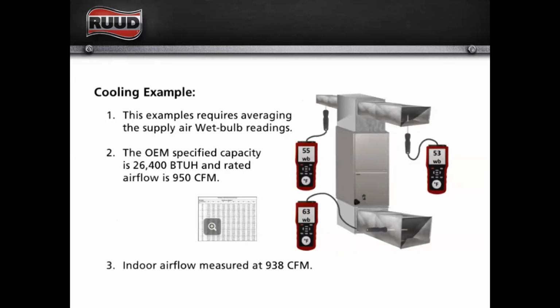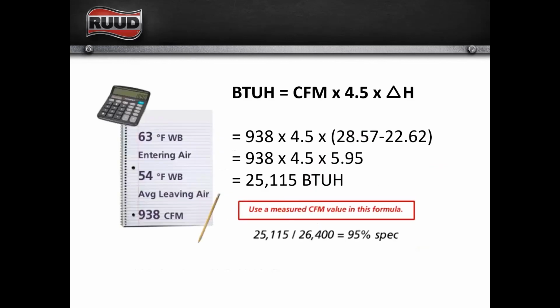Okay, so this is using CFM that we've got rated right here. So here's our example, right? We have got a manufacturer's specified capacity of 26,400 BTUs. Rated airflow is 950 CFM. Our actual airflow, which we measured by checking static, we compared the static to our blower table, and we measured 938 CFM.